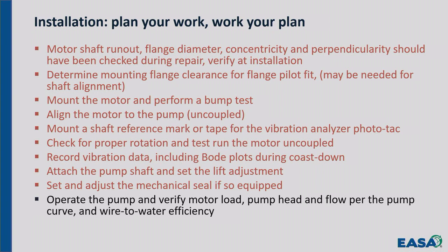Okay? Then you operate the pump, you verify the load on the motor, and you check the head and the flow on the pump, and you make sure that everything matches up on the pump curve. Okay. So let's look at some details related to that series of things. First, anybody have questions? Because we're going to see some more details on some of those. Okay?